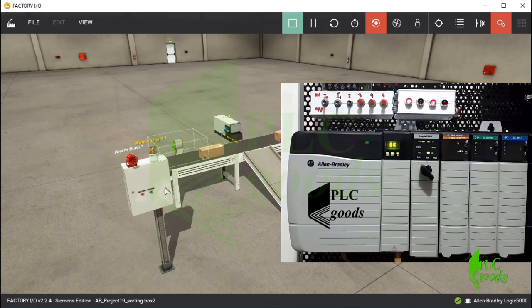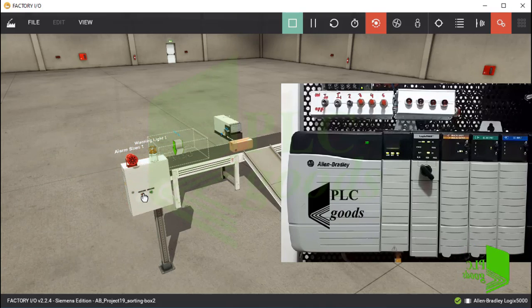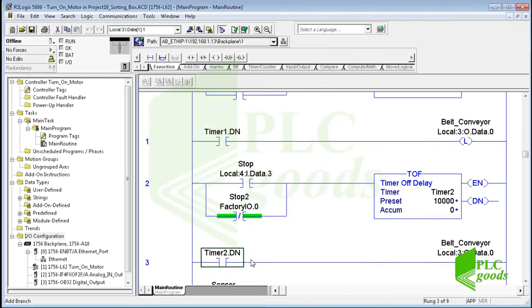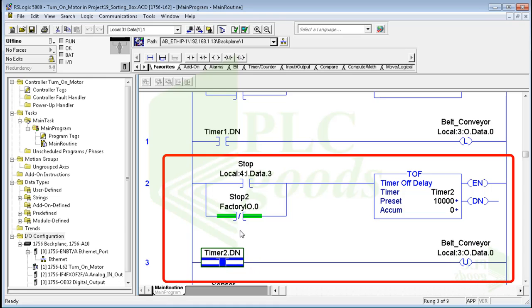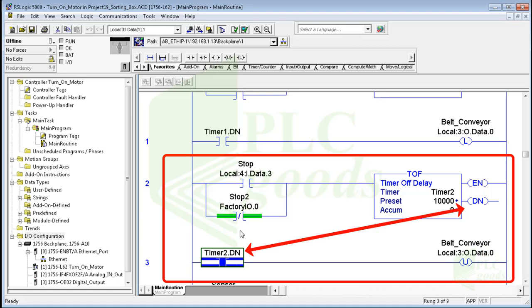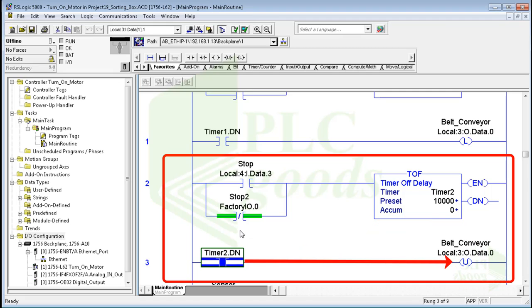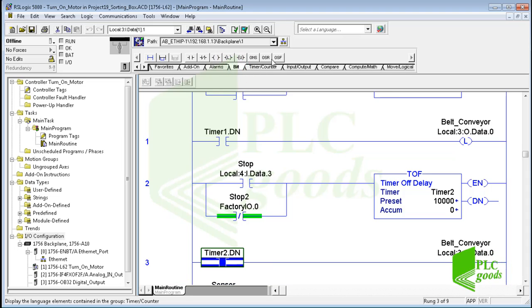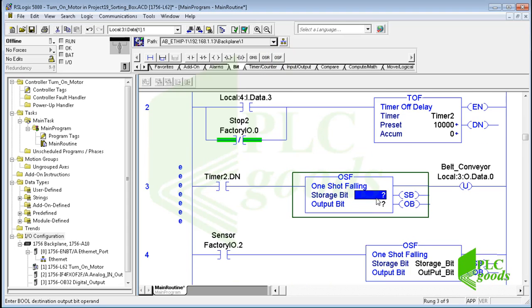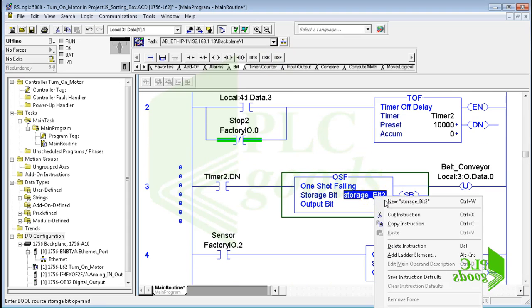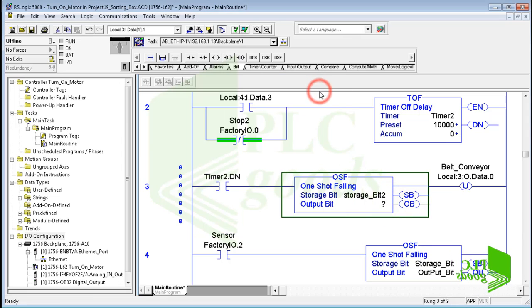Now, if I press the stop push button, the belt conveyor must be stopped after 10 seconds, but it stops immediately. Probably I need to modify the PLC program. When I press and then release the stop push button, the timer done bit will be on for 10 seconds — it makes the belt conveyor turn off immediately because I have used an unlatch instruction. To solve this problem, I can use a one-shot falling instruction to detect the moment when the done bit changes from 1 to 0 after 10 seconds.